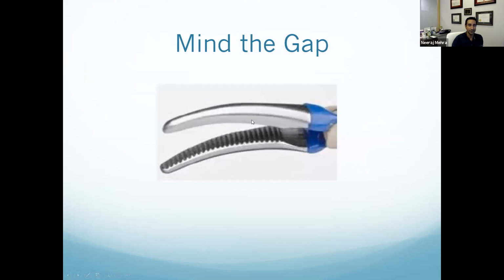Now, if you do use bipolar energy, a really important part is, as I said, electricity always flows through the path of least resistance. The thing that allows electrons to flow the easiest is metal. So sometimes you have a really fine, tiny bit of tissue, and if you don't have enough tissue separating the two ends of your instrument, and the ends are touching, then energy is going to flow through one end and back to the other end and isn't going to affect the tissue. So if you're using a bipolar instrument and you find that it's not working, part of it is that you just need to create a little bit of space so you don't have energy flowing from one side to the other. If anyone's ever come across that, usually it's at laparoscopy that you notice it.